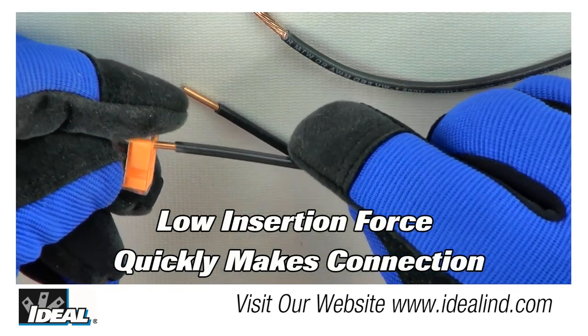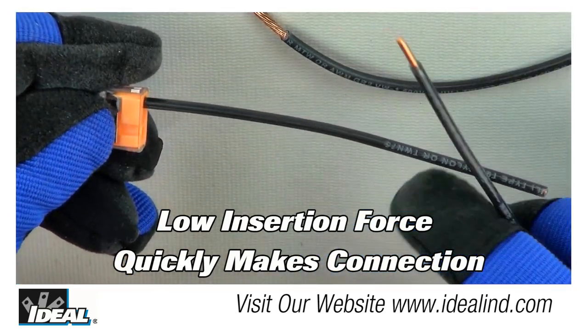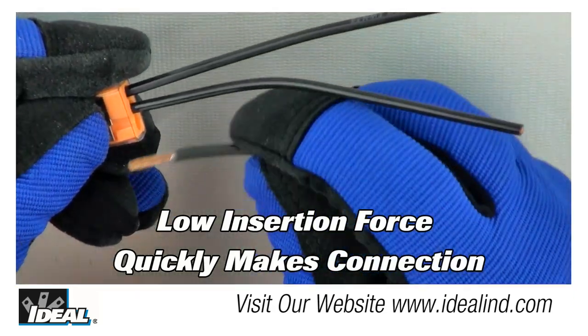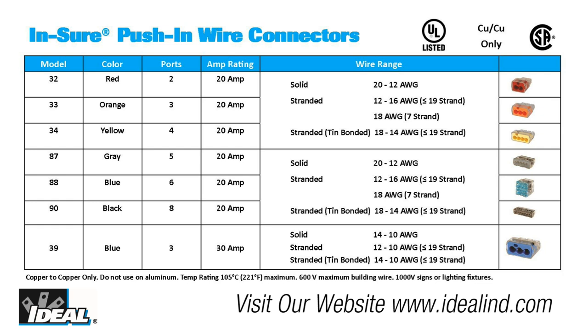The low insertion force makes it easy to push the solid or stranded wire fully into the connector, quickly completing the job. In-Sure push-in connectors are UL listed, CSA certified, and rated at 600 volts and 105 degrees Celsius for use on building wire, and 1000 volts in signs and lighting fixtures.